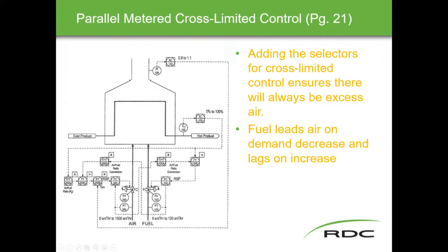When I have an increase in demand or a call for heat, my fuel is going to lag on an increase, which means I'm going to open the air valve a little bit first, that signal here first, before I open up the fuel valve, to ensure that, again, I don't have that puff of black smoke as we go up there. And that's really what the whole process is designed for.